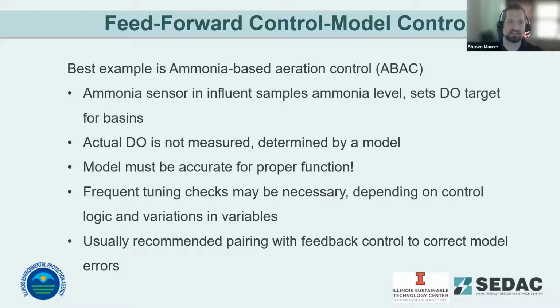And so what we tend to see is with this kind of basic feed forward ammonia control, it works best for plants that have a consistent influent coming in. They don't have wide swings in loading rates, or things like large swings in I&I, or an industrial client that may dump slugs into the system. Usually what we see, as with the feedback control for ammonium, is this gets paired with a DO sensor in order to limit those swings. So you have kind of a combination of feed forward control for the ammonia sensor that's providing more rapid response for your facility. And then your DO is providing feedback to the system to keep you from swinging and hunting with your trying to hit those target set points.